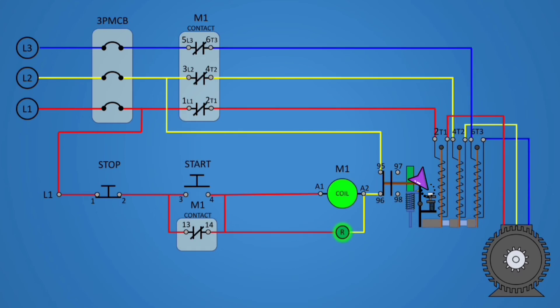The current adjustment screw is used to set the tripping current of the motor. A current range is indicated on the motor's nameplate or by calculating the current protection for the motor.